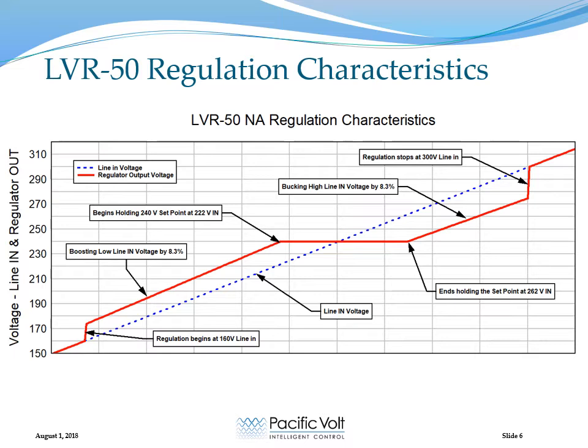This chart illustrates the regulation characteristics of the low voltage regulator. The blue line represents an increasing input voltage to the regulator. At about 160 volts, the regulator will turn on and it will start to boost the voltage 8.3%. As the input voltage continues to rise, it will continue boosting as much as it can until the output reaches the set point, at which time the output will remain constant while the input voltage continues to rise until the dynamic range of the regulator is exceeded. Then it will continue to buck the input voltage, 8.3%, as the voltage continues to rise until it reaches 300 volts, at which point it will shut off and stop regulating.